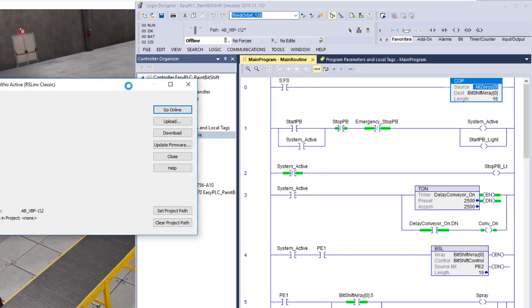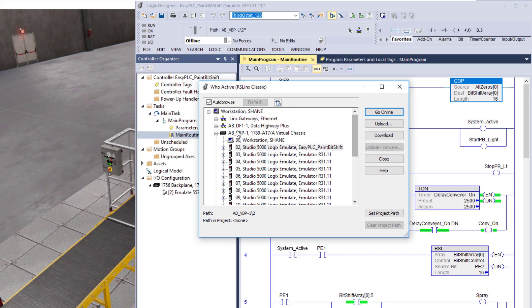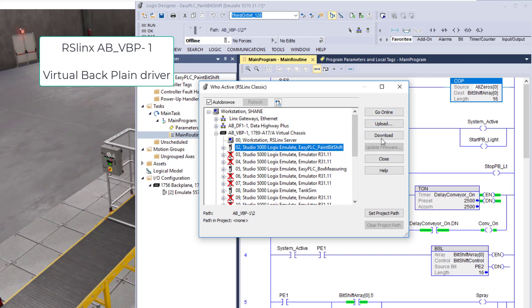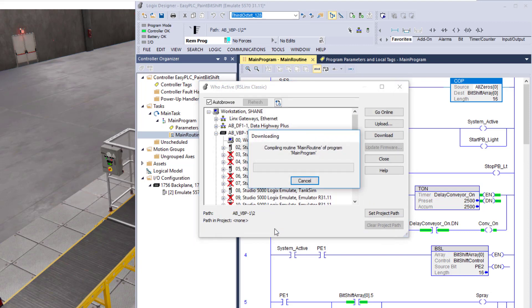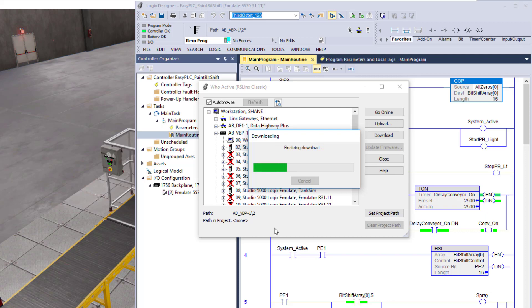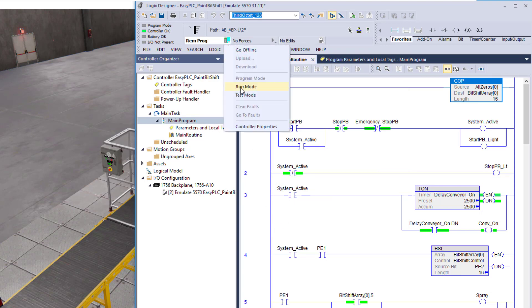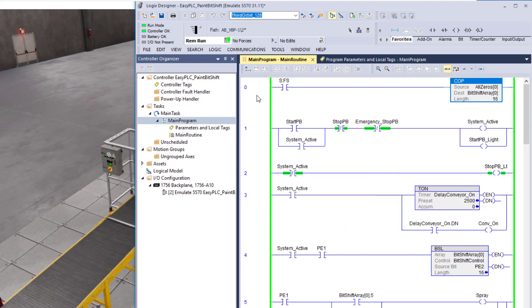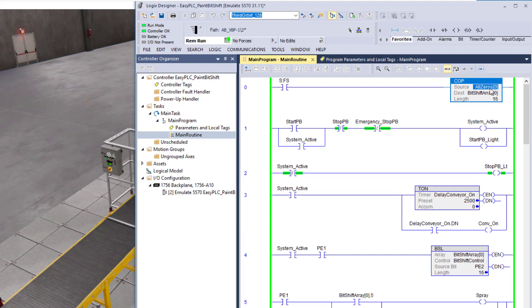Let's go ahead and download to this processor. I'm going to select ABVBP1, which is my virtual back plane, second slot. I'll hit download. When I hit download, we're going to see what the first scan does — it's going to write all zeros in there and clear the bit shift so we start the program from scratch, whether it be a power upset or a general system start. As soon as I change this to run, it's going to change. It did a first scan. Now let's look at our data again — you can see it's all zeros. That first scan bit is really quick and it loaded all zeros in here.